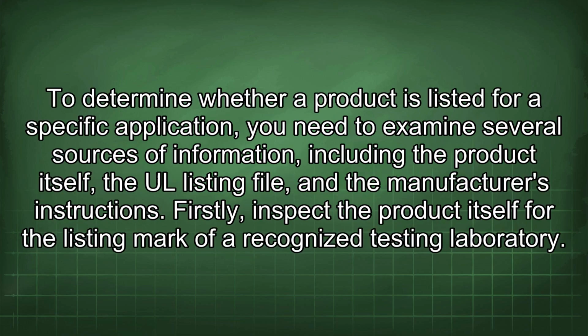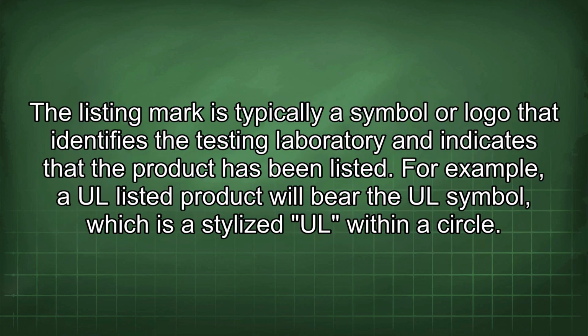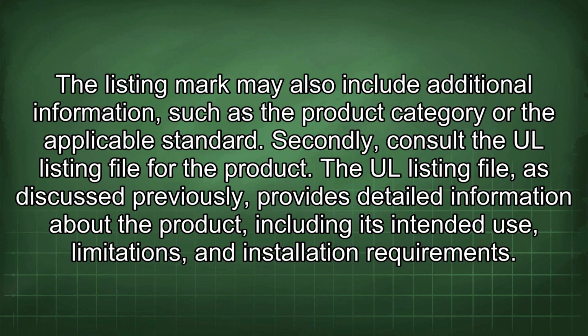To determine whether a product is listed for a specific application, you need to examine several sources of information, including the product itself, the UL listing file, and the manufacturer's instructions. Firstly, inspect the product itself for the listing mark of a recognized testing laboratory. The listing mark is typically a symbol or logo that identifies the testing laboratory and indicates that the product has been listed. For example, a UL listed product will bear the UL symbol, which is a stylized UL within a circle. The listing mark may also include additional information such as the product category or the applicable standard.